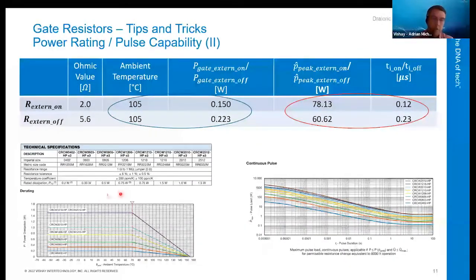But if your ambient temperature is higher than 70 degrees C, you also have to implement a derating factor, highlighted in the derating graphs. So you cannot use these values anymore; you have to transform them via the higher temperature with the derating factor. And now you have, first of all, one case size you can use in your application.